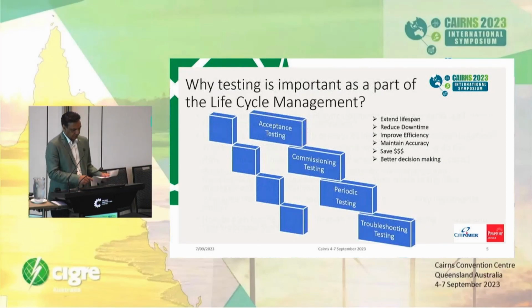So let's look at why testing is important for life cycle management. We can divide that into 4 main parts. First is the acceptance, or you can say the compliance to the standards and specifications. It is very important to test the device or system to the international standards and any specific client requirements. Then comes the commissioning testing, because many devices which work fine independently can cause trouble when tested as part of a system. Once the system is commissioned and running, periodic testing is paramount to ensure that the data being received is accurate and reliable. And if there is any malfunction in the system, then troubleshooting testing must be done to get the system up and running as quickly as possible.